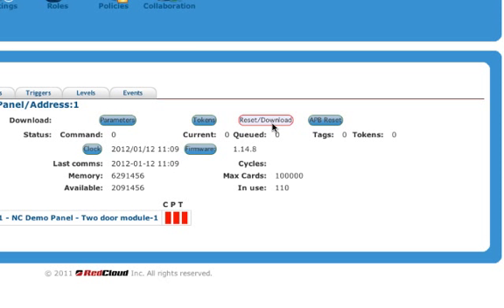The most important thing here is to remember that as part of the process, regardless of whether this is a brand new panel out of the box or whether it's a panel that you got off the shelf that was being utilized someplace else, you still need to download the firmware and do a reset download to the panel regardless of whether or not you see that panel ID mismatch.